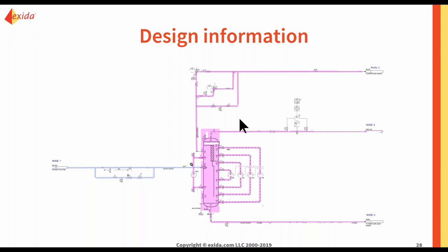And the other path that some facilitators might take would be to assume that the design limit of the drum won't be breached, so there won't be a valid scenario. But if the design can actually be breached, you're actively ignoring a potential hazard, and also you are reducing the SIL level that's required on the SIF. So you are under-designing your safety system, which is even worse in a lot of ways.